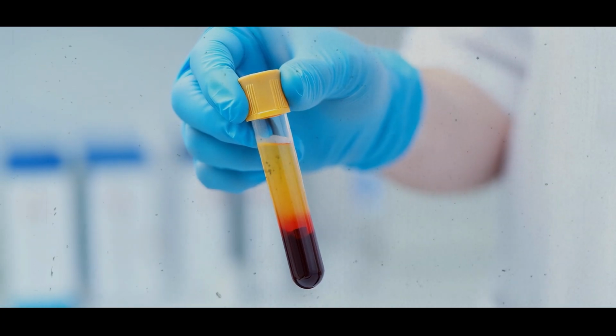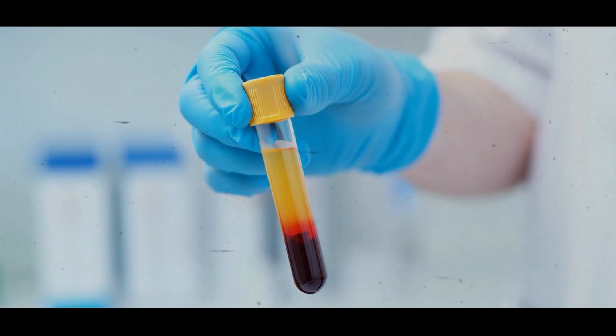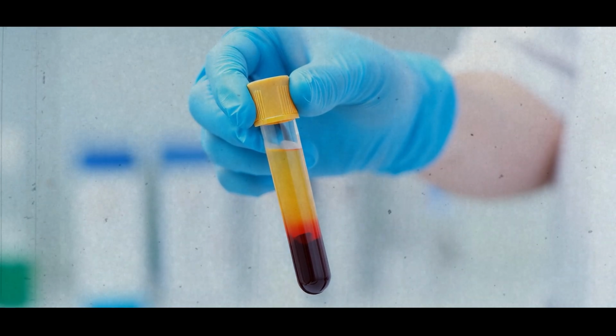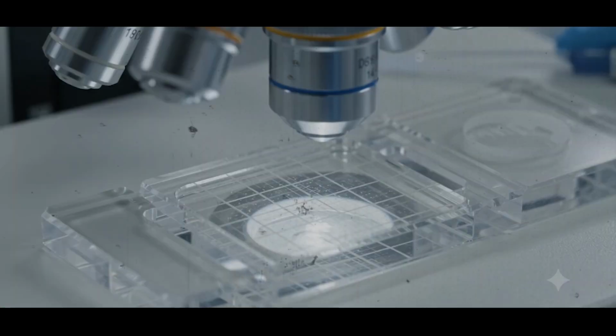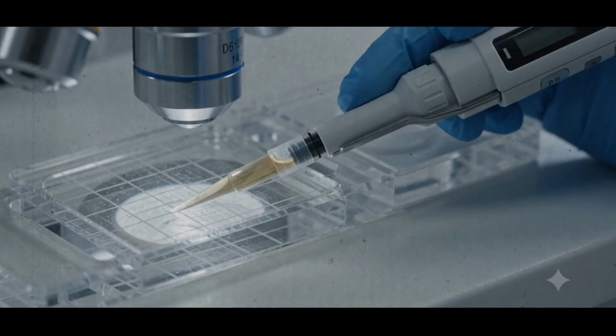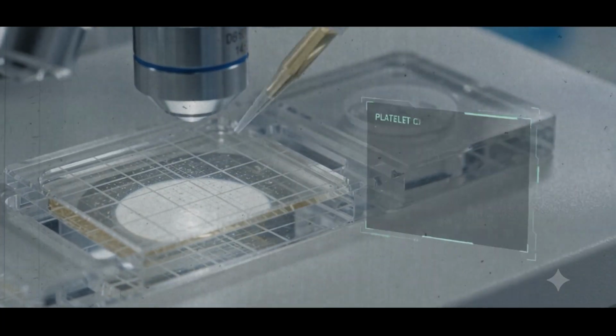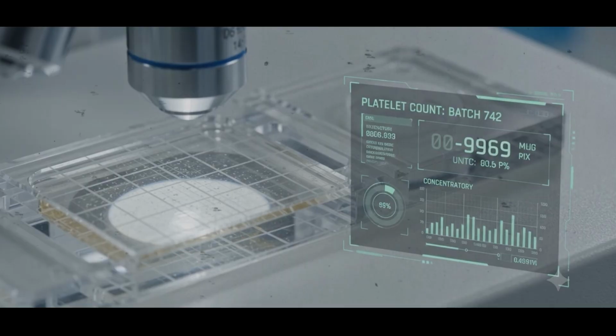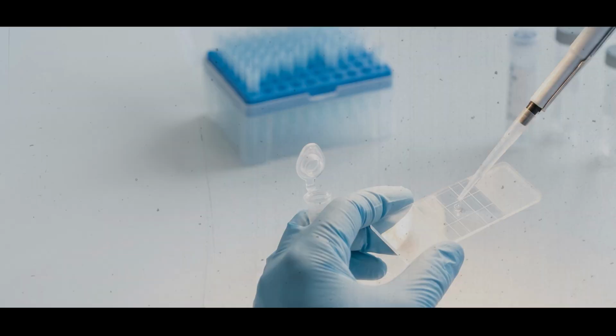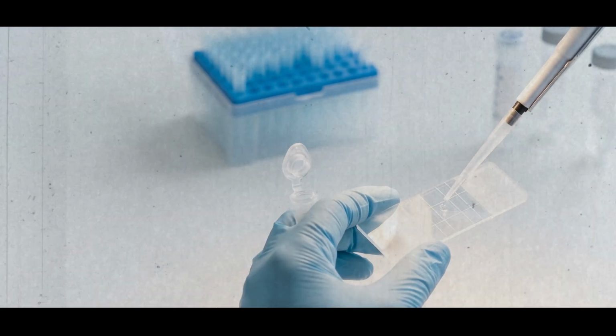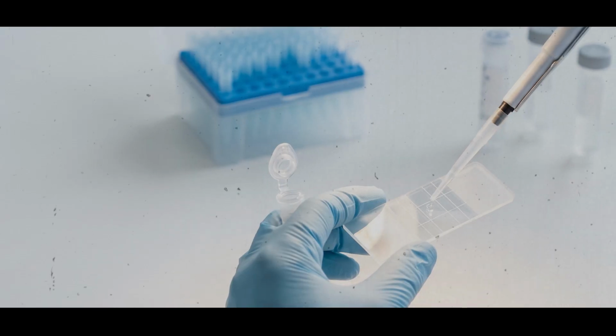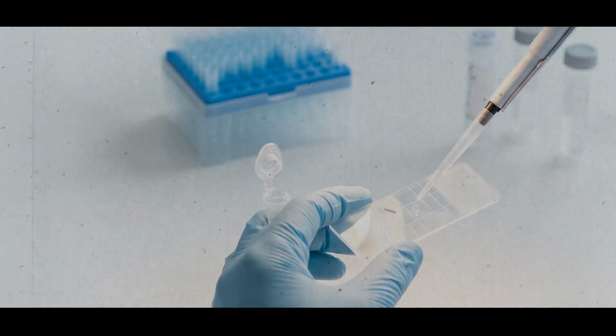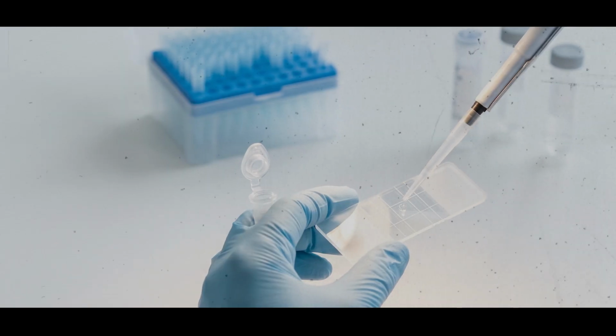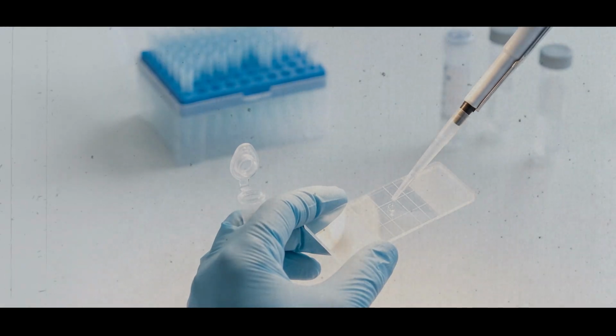You have to be able to test each sample on a high volume hemocytometer that tests at the high end of the platelet counts, so the settings have to allow for high concentration platelets. Normal hemocytometers and normal laboratories aren't calibrated for these high concentration solutions. So there are specialized high concentration hemocytometers, such as the Beckman or Horiba, that are calibrated to count the high concentration.